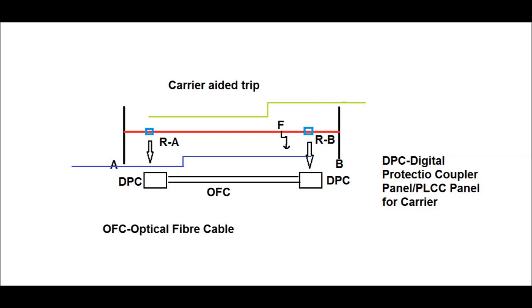The relay at the A end, that is distance relay A, will receive it as a carrier receive, and since zone 2 pickup as well as carrier receive are present, it will send a trip signal to the respective circuit breaker of the transmission line and isolate the fault. Therefore, for carrier aided protection trip, we require a carrier, which may be an optical fiber cable or a PLCC channel.